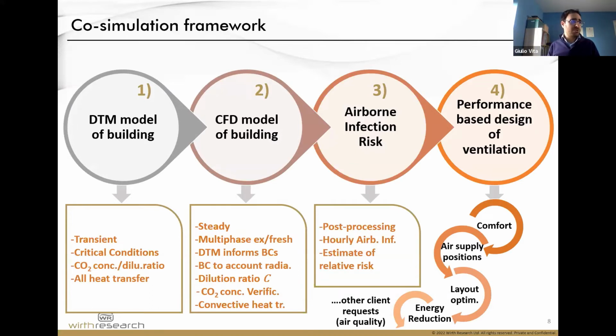And we came up with this co-simulation framework where first we simulate the DTM. We have a transient solution where critical conditions are understood. We take those critical conditions. What I mean by taking is surface temperatures and results to inform our CFD. So we model the CFD in a way that the surfaces are defined in a similar way as the DTM, and they are then informed by the DTM, so the boundary conditions reflect the results of the DTM.